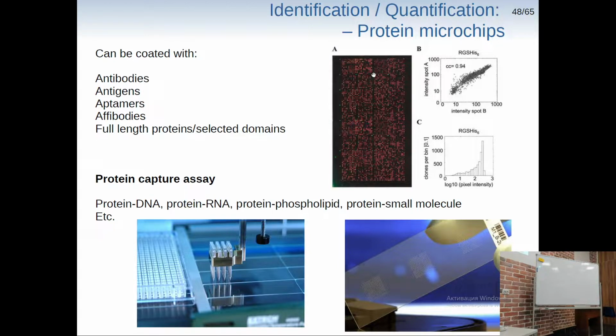And now you've calibrated only that your instrument is able to measure this intensity at the center of the field and at some position. And you need to calibrate your chip because you can actually have a little bit different concentration of your solutions here, for instance, and so on. So you can input here something that will be able to bind to some protein which is not in your sample, which you add externally. And then you can see whether it binds and what is the intensity of this binding here. And so you will be able to calibrate your sample.